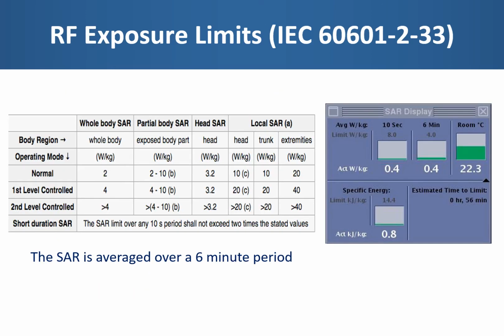So in terms of these exposure limits, IEC 60601 is part of a series of international standards for medical electrical equipment covering their basic safety and essential performance for both equipment and systems. Part 2-33 discusses the particular requirements for the safety of magnetic resonance equipment for medical diagnosis. And this table shows the exposure limits for RF in typical MRI systems. An MRI scanner can be operated in either the normal or the first level controlled mode, and very rarely in a second level control mode. And in the first level mode, for example, the whole body power deposition cannot exceed 4 watts per kilogram.